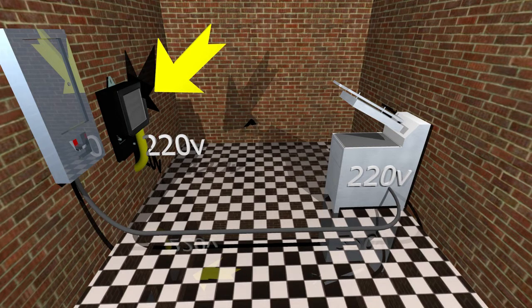Excessively long cable runs or underrated cables can result in voltage drop at the machine. With the machine running, check that a minimum of 220 volts is present per phase at the clam grill. Anything below this can cause the grill to malfunction. If the voltage is below 220 volts at the machine, check the voltage of the incoming supply at the meter. If the voltage at the incoming supply is correct and the voltage at the machine is low, then upgrade the cable installation to the machine.